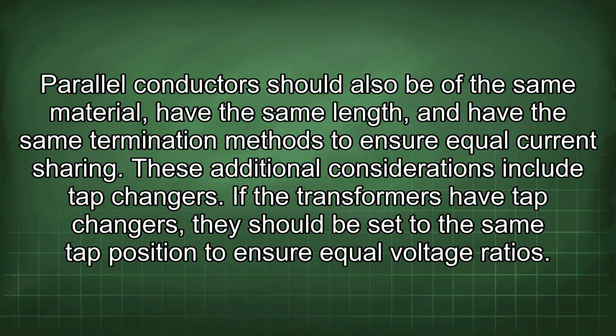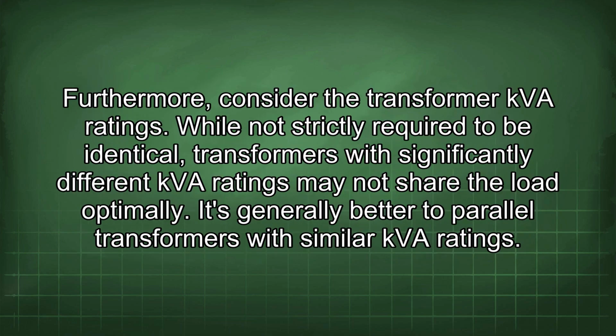These additional considerations include tap changers. If the transformers have tap changers, they should be set to the same tap position to ensure equal voltage ratios. Furthermore, consider the transformer kVA ratings. While not strictly required to be identical, transformers with significantly different kVA ratings may not share the load optimally. It's generally better to parallel transformers with similar kVA ratings.